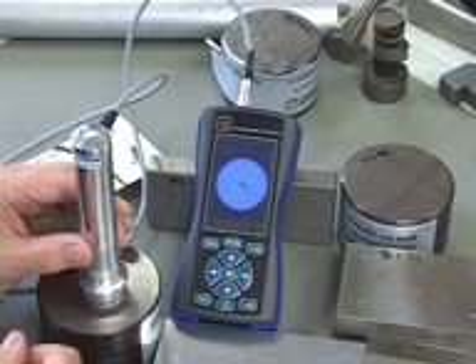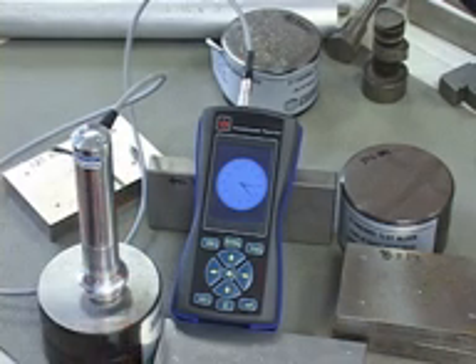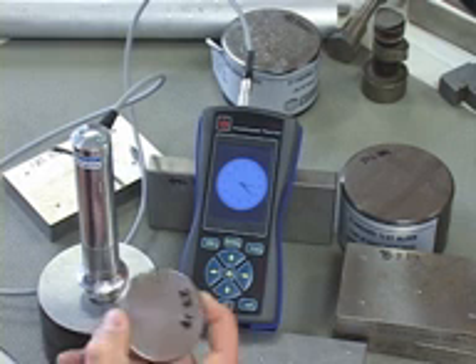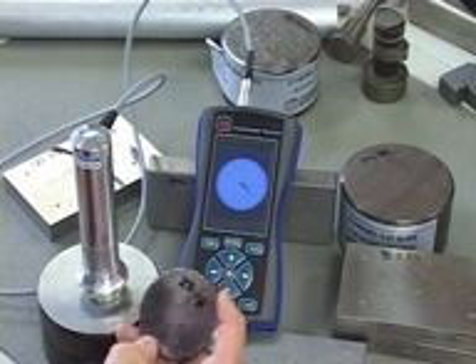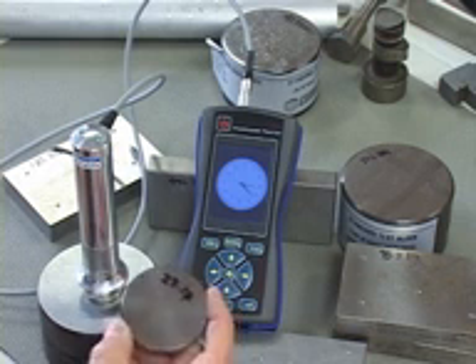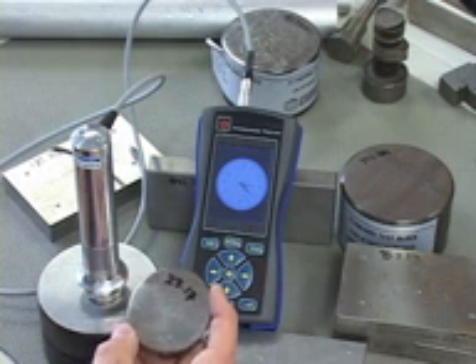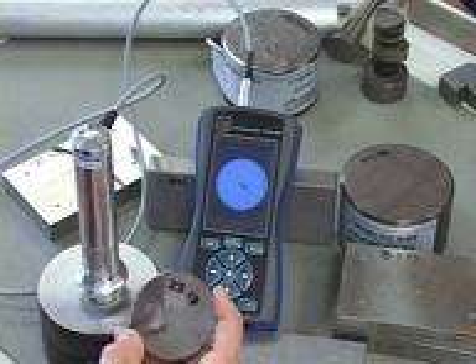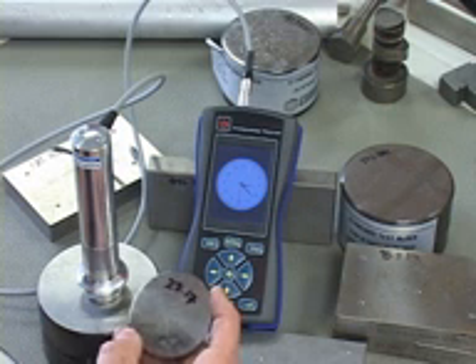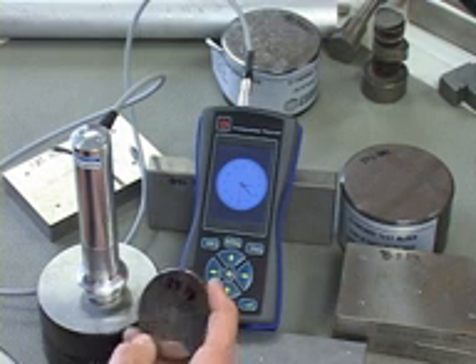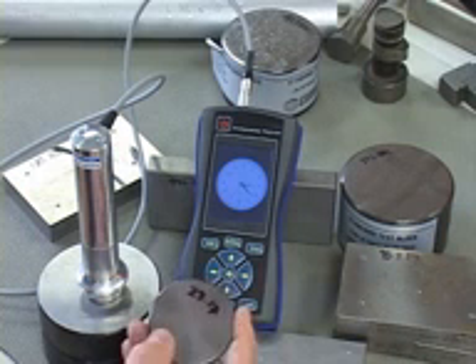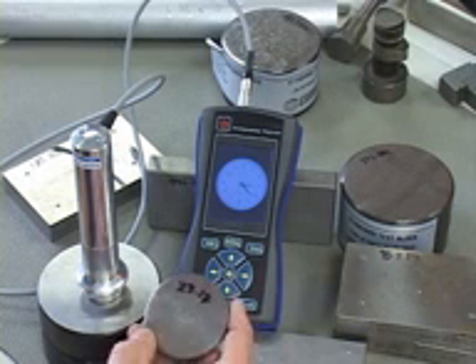the test is done. So what I'm going to do here is to do a test on 3 different test blocks. These are all HRC test blocks. They are made in the US, they are NIST traceable, and these are an option that goes with the device. The reason we sell them as an option is because many customers already have a bench tester with similar calibration blocks, so there's no point buying a secondary group.